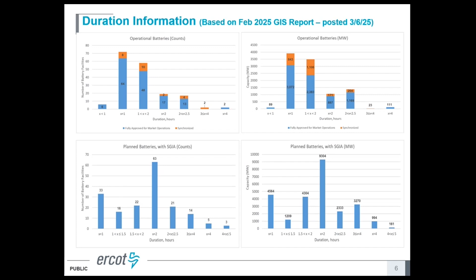What this means is that in ERCOT, with shorter duration, batteries are having to deal with the minimum state of charge point and the maximum state of charge point more frequently than if these were 4 hour batteries.